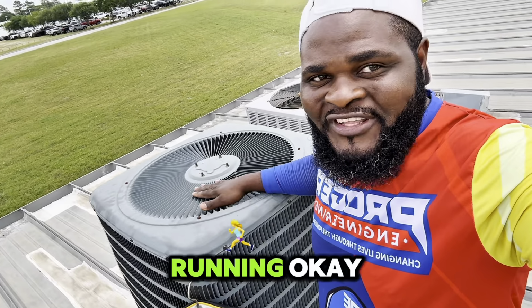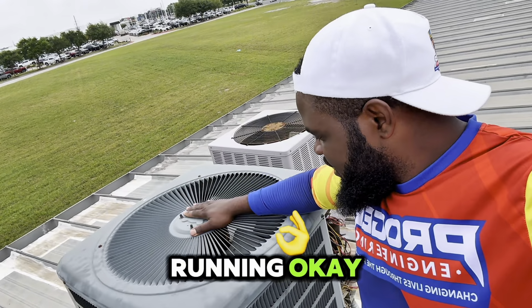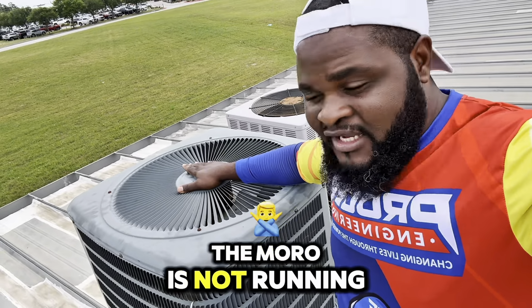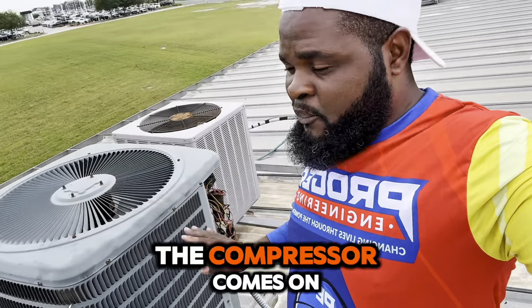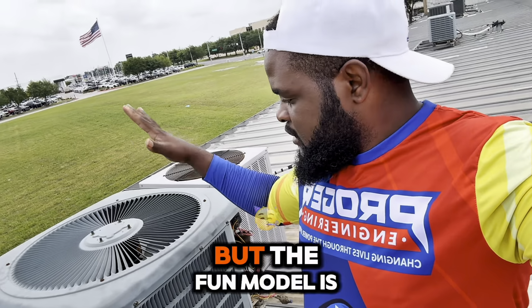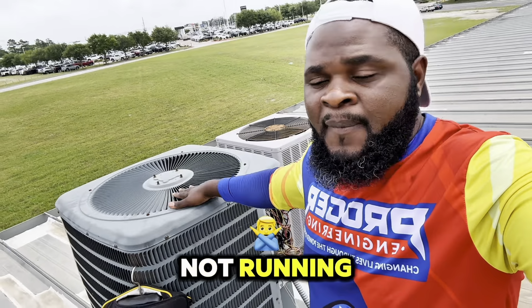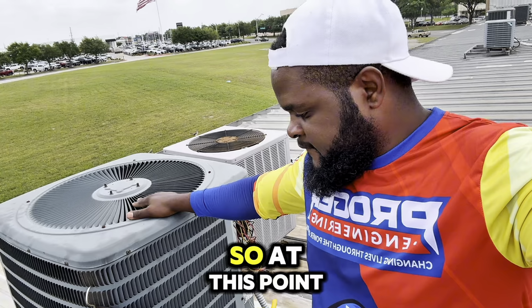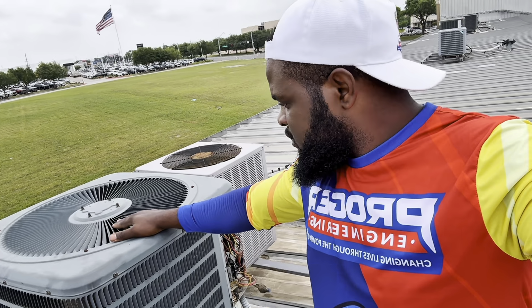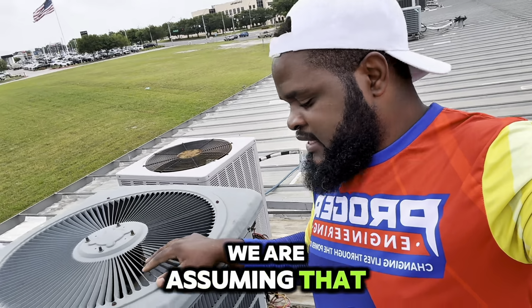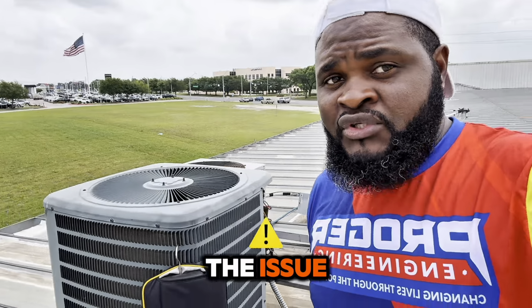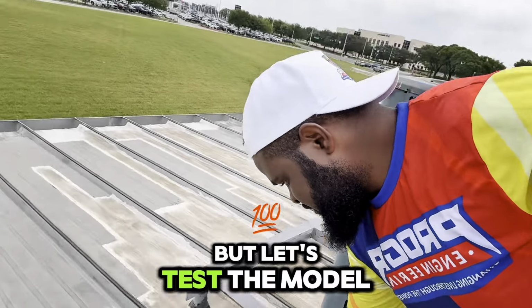The motor is not running. Okay, the motor is not running. The compressor comes on, but the fan motor is not running. So at this point, we are assuming that the motor should be the issue, but let's test the motor.